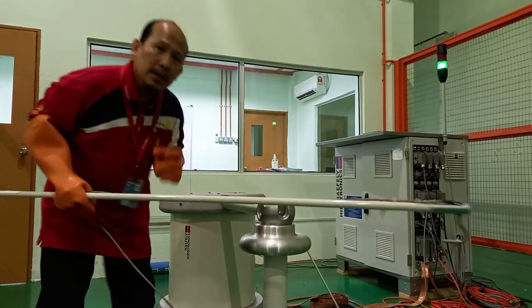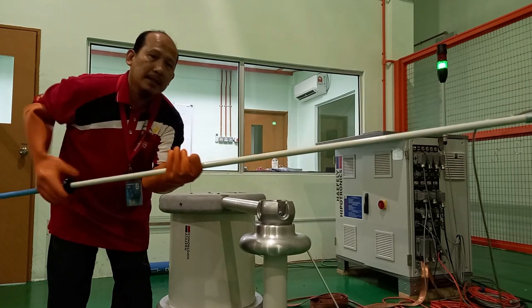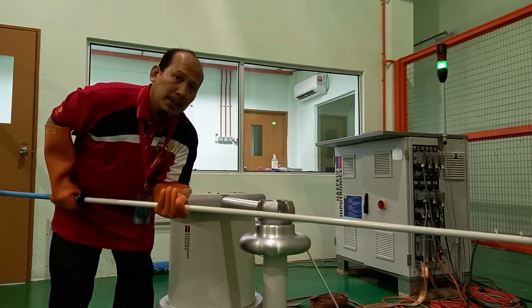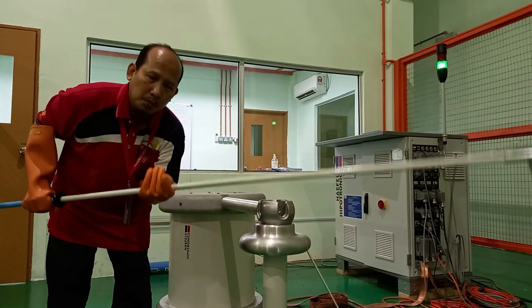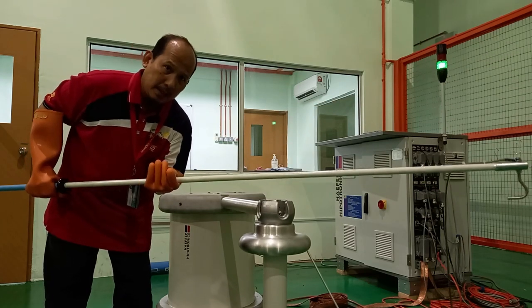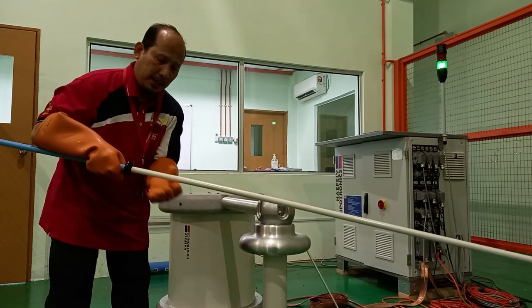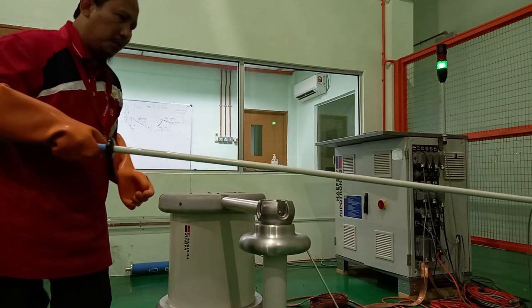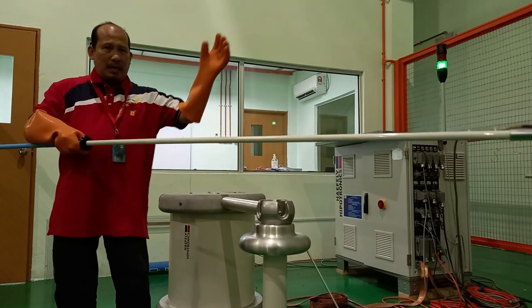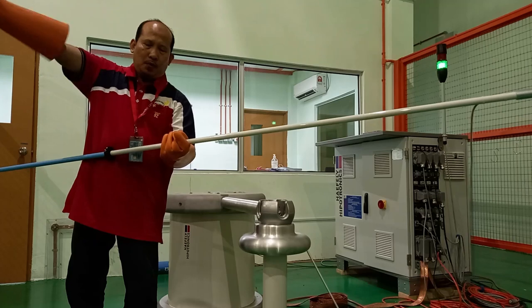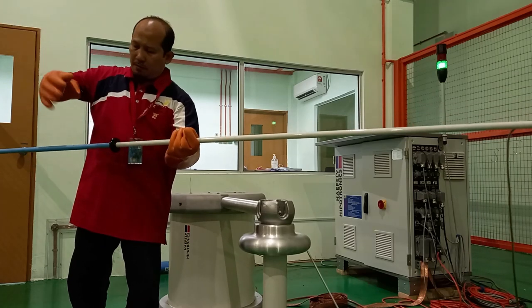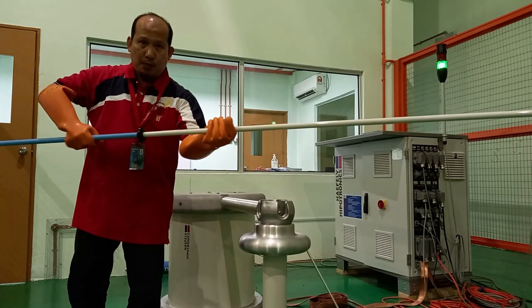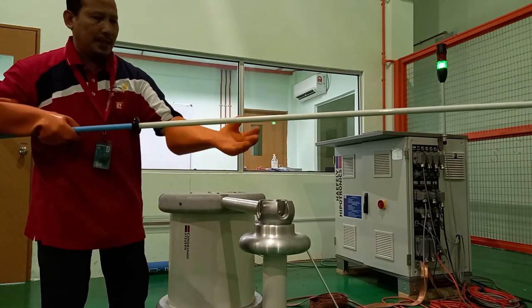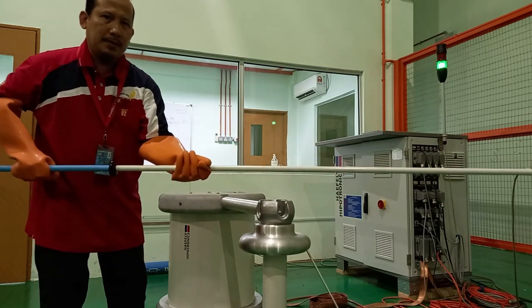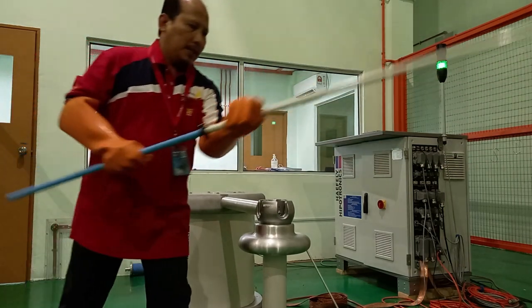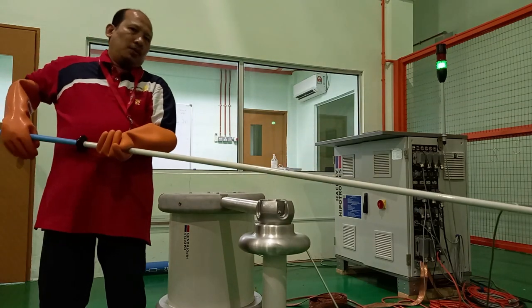implement double safety. You have to discharge again, so we use the earthing rod. Please ensure that every time you use this, you use your left hand. If you are right-handed, hold it on the right side like this, and your left hand hold like that. And then ensure that the cable is not that close to you.